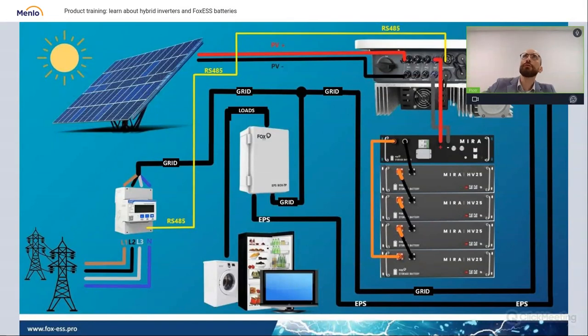electrical shock for the technician working on that blacked out line, because if you output energy to your local grid, this energy will flow to the distributor's grid also. And if there is no hole in this system, no disconnection within this line, this power goes then to the transformer that transforms it to high voltages and sends it back. So there's a risk of killing someone.